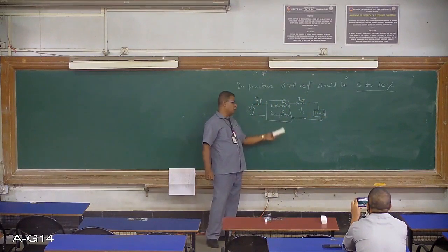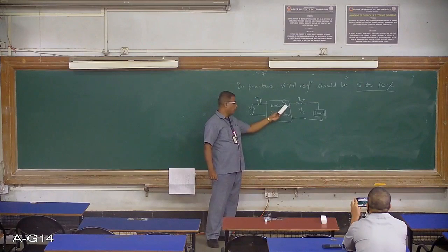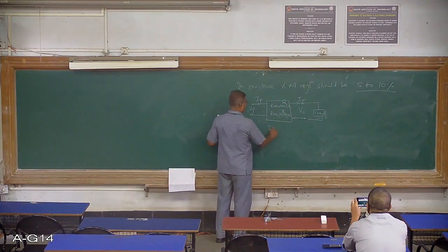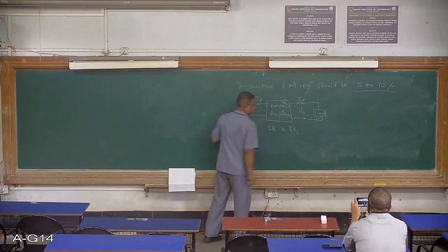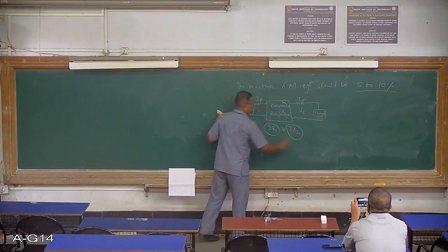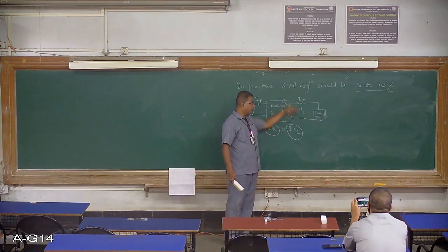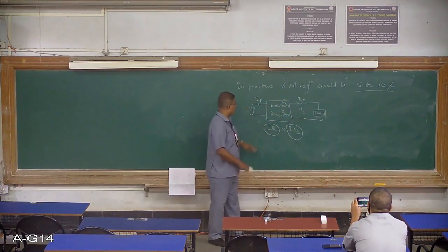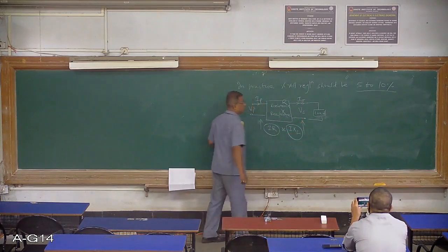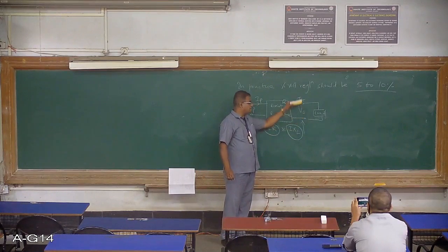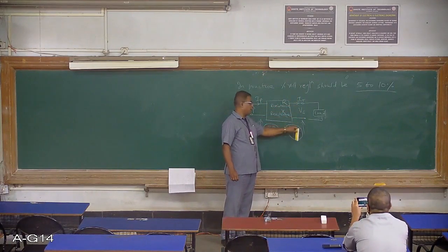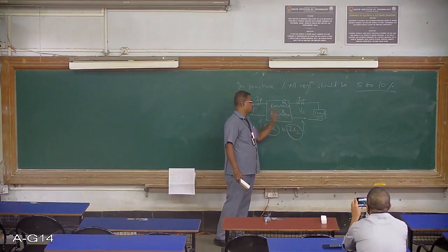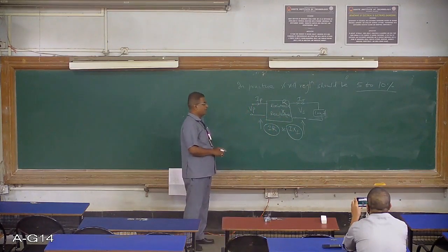So whenever current flows in the transformer through the resistance R and leakage reactance XL, there will be a voltage drop IR and IXL. Due to these voltage drops, a part of the voltage reduces. With increase in load, current increases. With increase in current, the drops increase. And whenever the voltage drops increase, the terminal voltage definitely decreases. So therefore, the terminal voltage decreases due to the resistance of the transformer and leakage reactance of the transformer. Okay? So this fact you can easily understand.